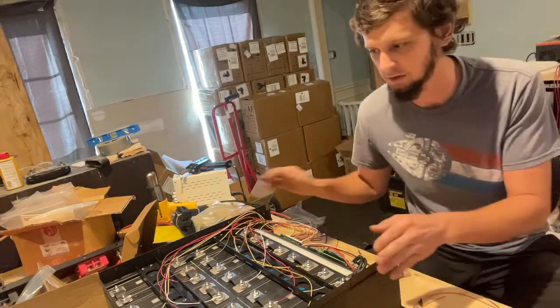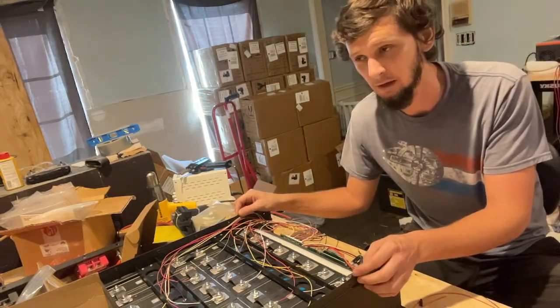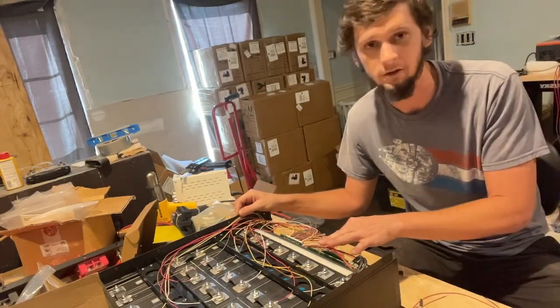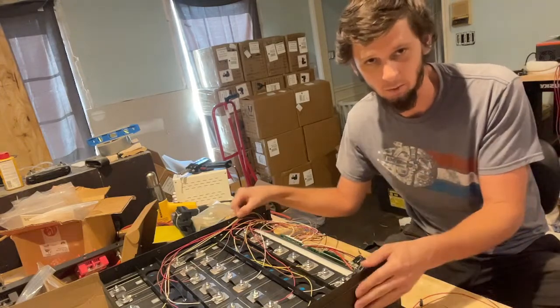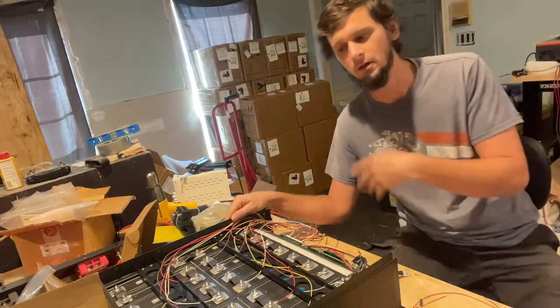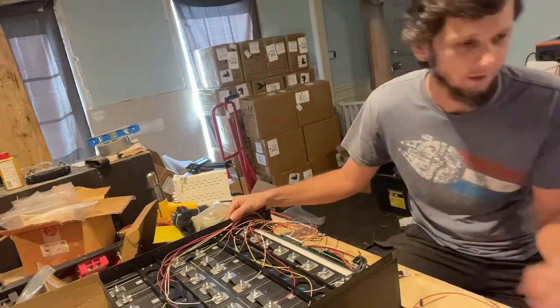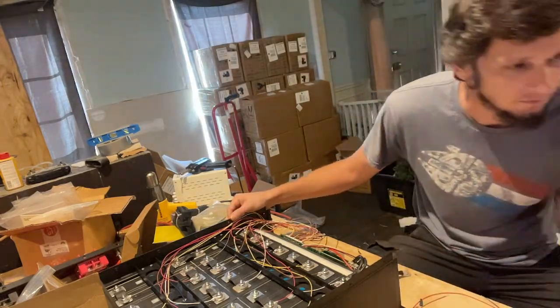This one's actually 130 amp hour. The BMS is 100 amps, so you can pull about 4.8 kilowatts out of it at a time, but it's 130 amp hours of storage capacity at 48 volts.